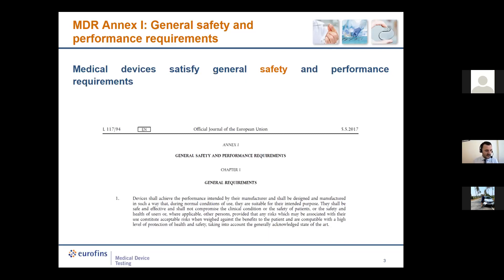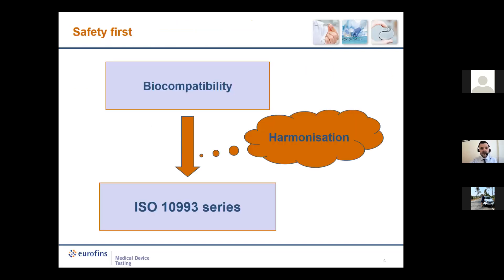The MDR also requires taking into account the compatibility between materials and substances with biological tissue, cells, body fluids — considering the intended purpose — and where relevant, absorption, distribution, metabolism, and excretion. The impact of the process on material properties must also be accounted for during the biological evaluation. When dealing with biocompatibility, we need a well-defined approach providing a scientific and robust proof, one that saves time and cost and is accepted by notified bodies and competent authorities. To perform this assessment, we rely on the ISO 10993 series.